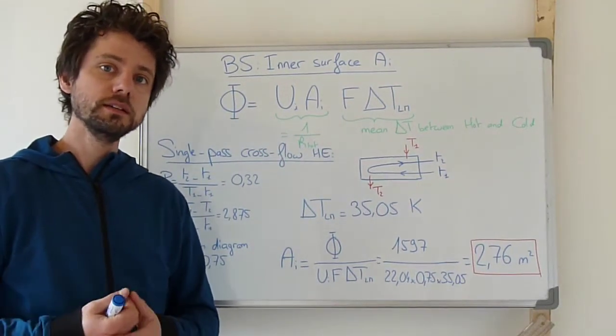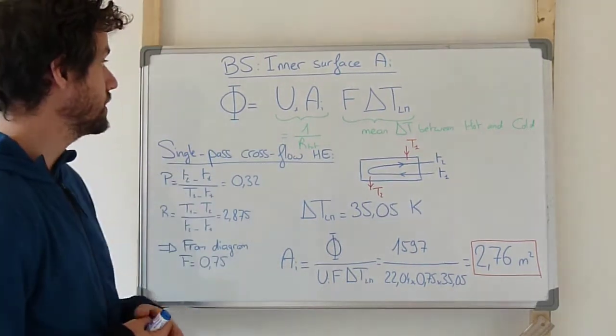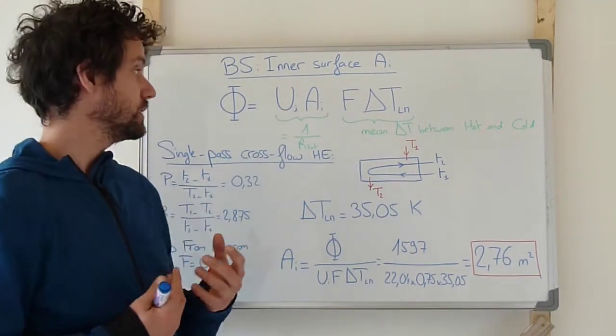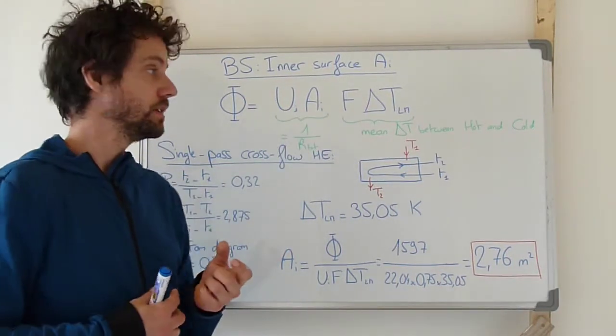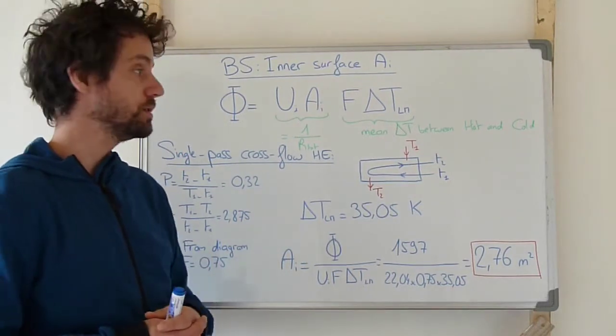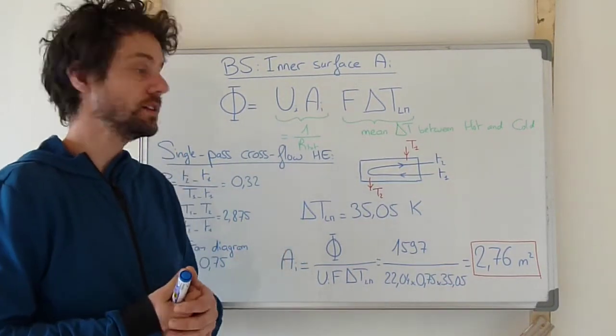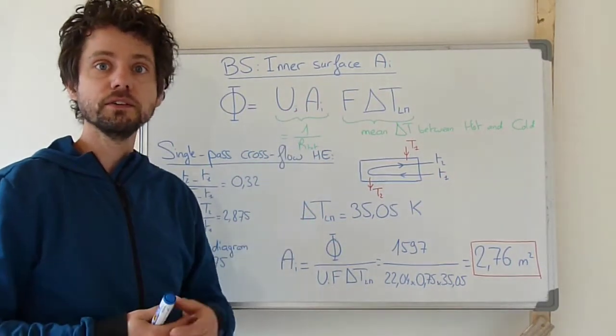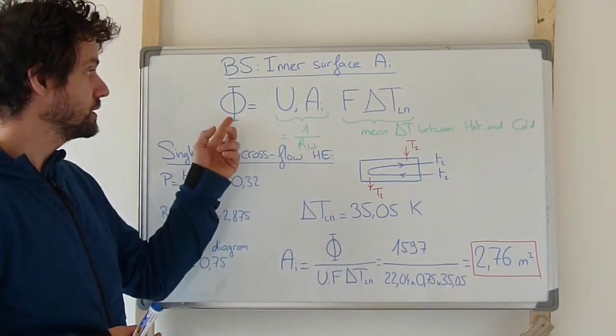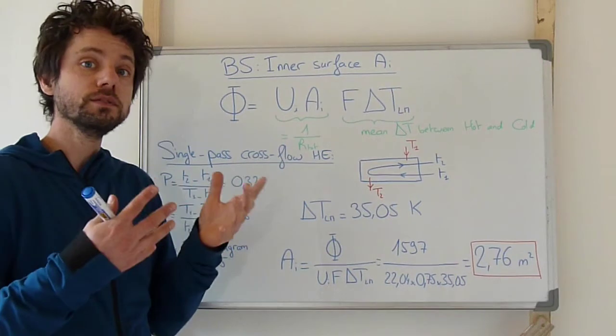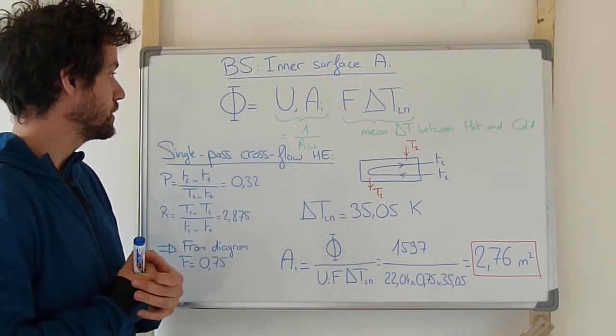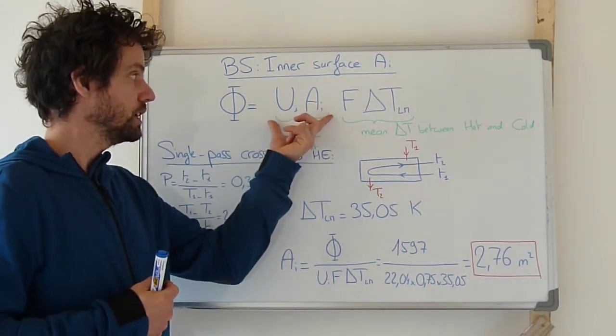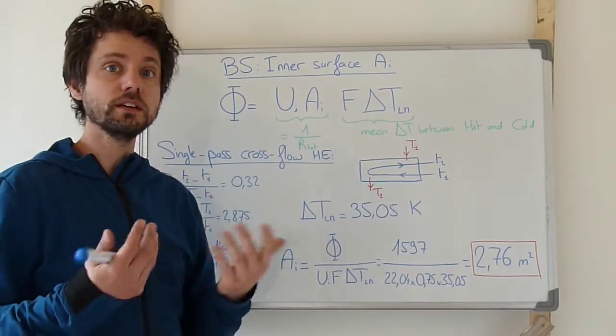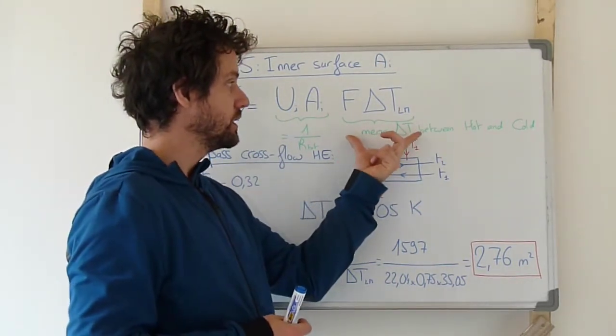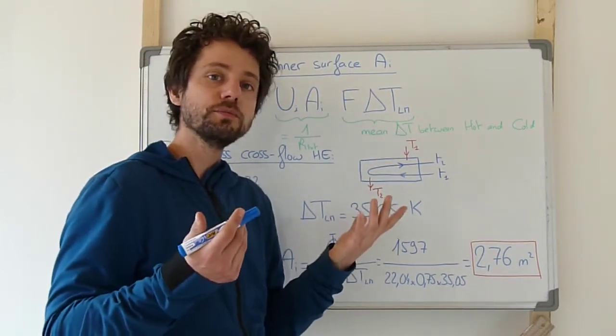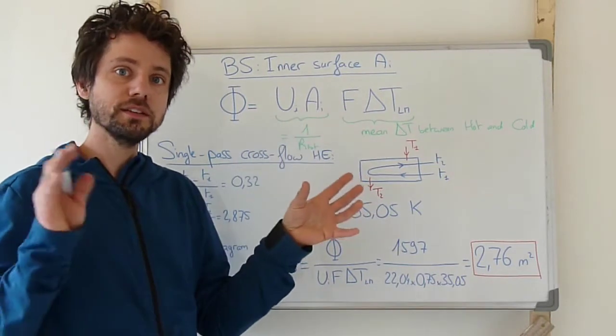So now that we have calculated the overall heat transfer coefficient on the inner side, Ui, what we want to calculate is the heat transfer area that is needed in order to size this heat exchanger, and from this we will then calculate the length of the tube. So we can write that the total heat flux between the hot and the cold fluid is equal to Ui times Ai, so that's the inverse of the total heat transfer resistance, multiplied by the average difference of temperature between the hot and the cold side.